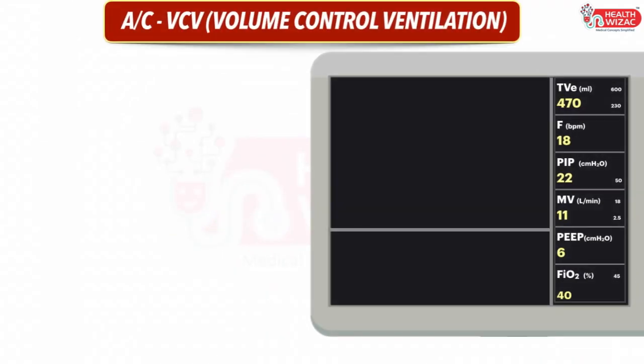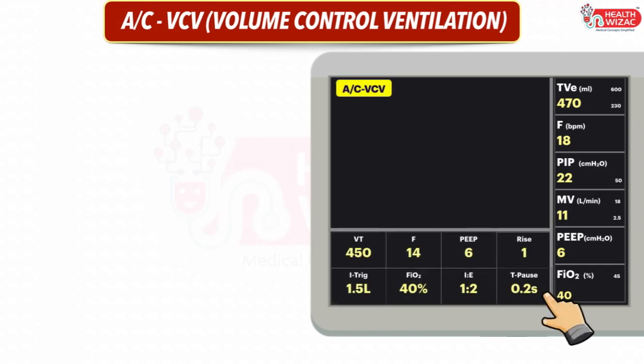The first mode is Volume Control Ventilation. In this mode we have to set tidal volume, frequency, PEEP, rise time, inspiratory trigger, FiO2, I:E ratio, and pause time.